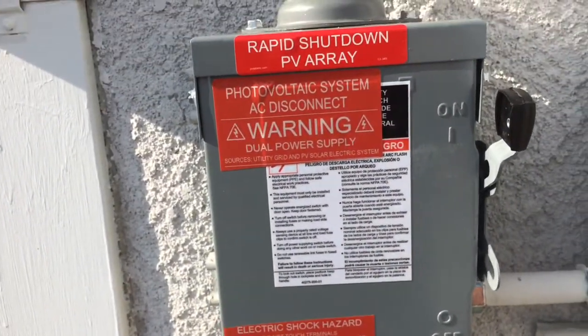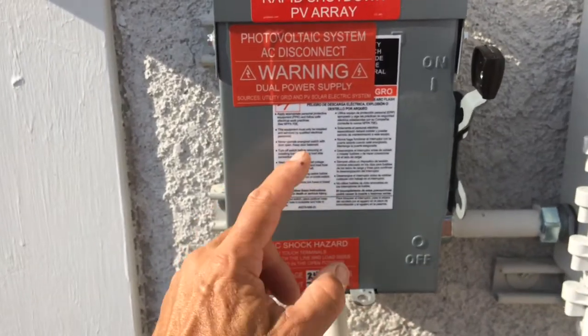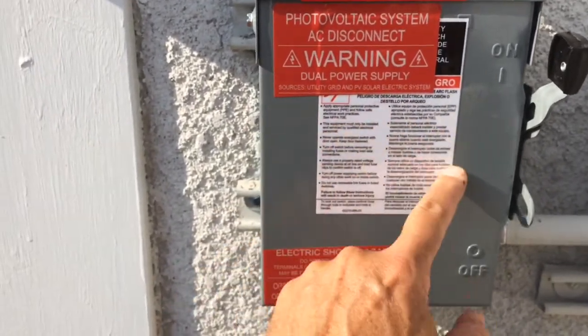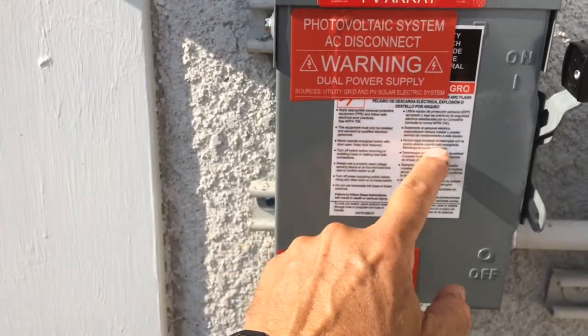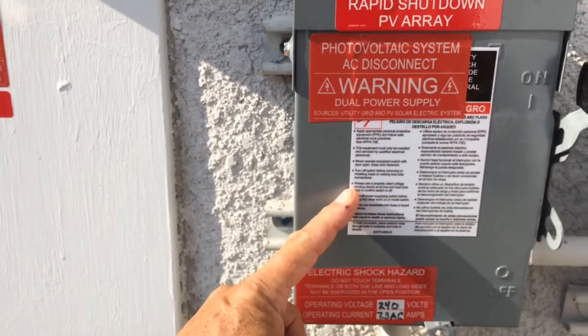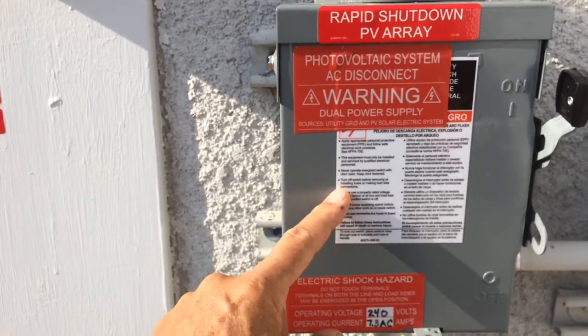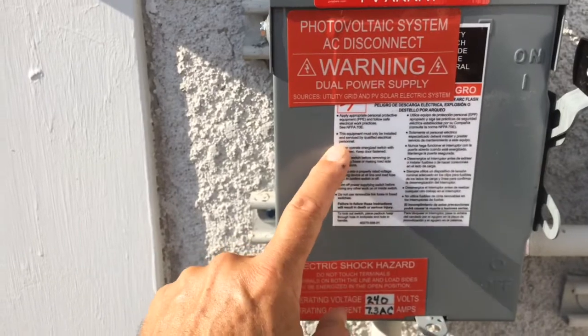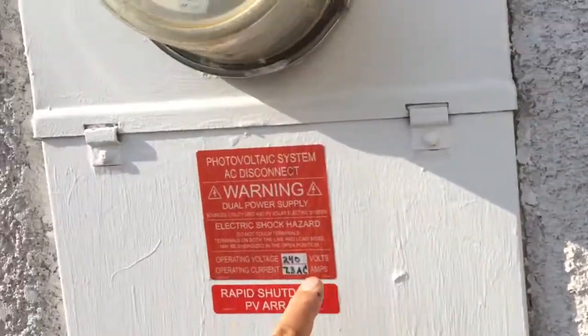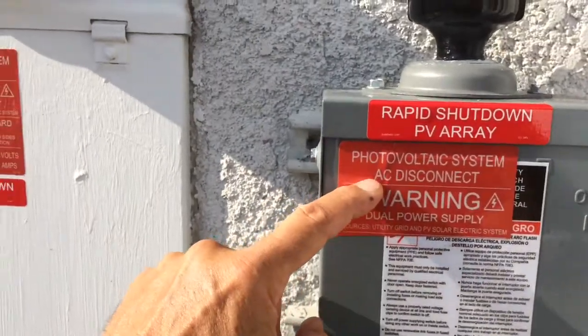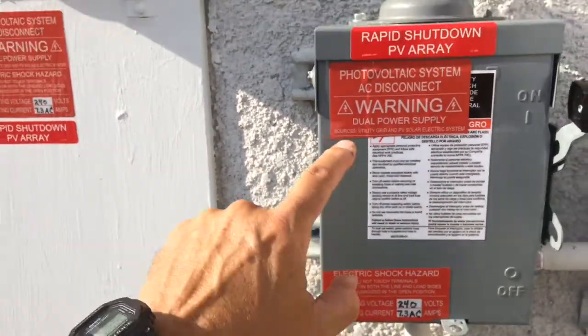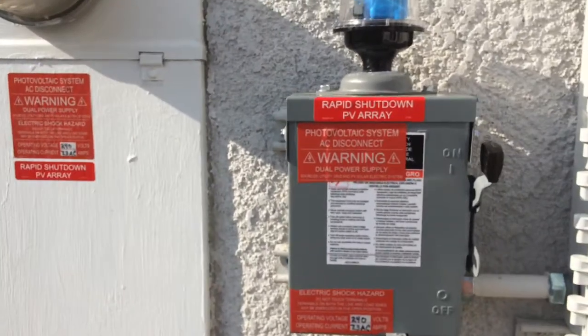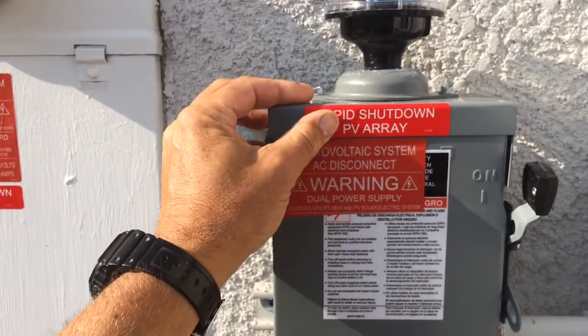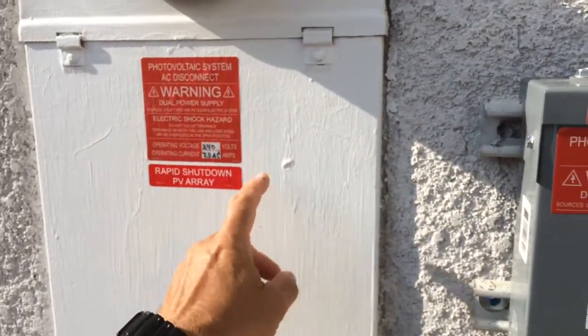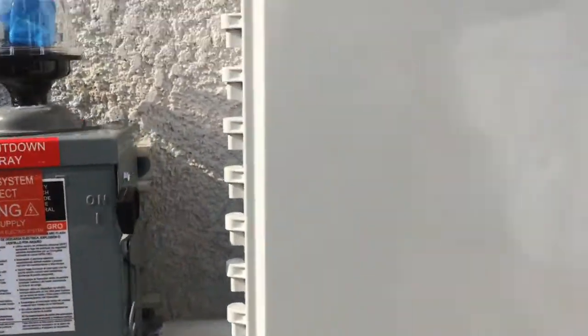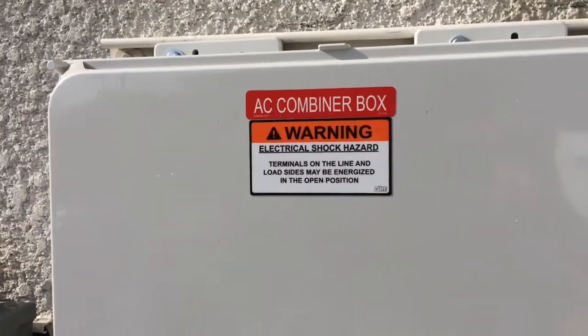And then here's another special case where the utility disconnect, there was language on the sticker, the original manufacturer's sticker, and my interpretation of the code was that you're not supposed to cover this language. So I had to just take this sticker here and cut it, and I just put two pieces, this piece and this piece, you can kind of see. Again, rapid shutdown on both this panel and this panel. And then on the combiner box, I labeled the combiner box with this warning here.